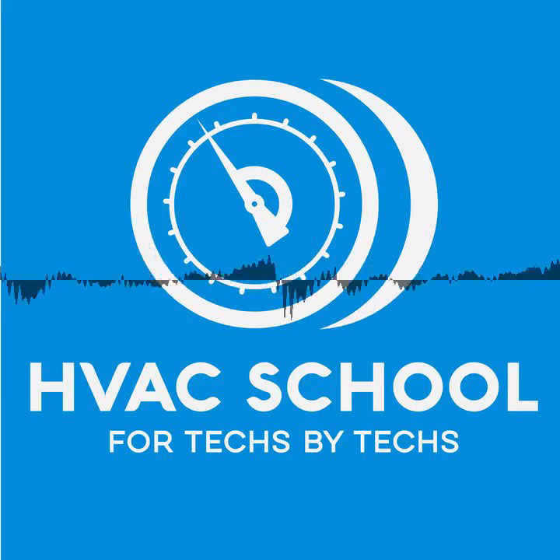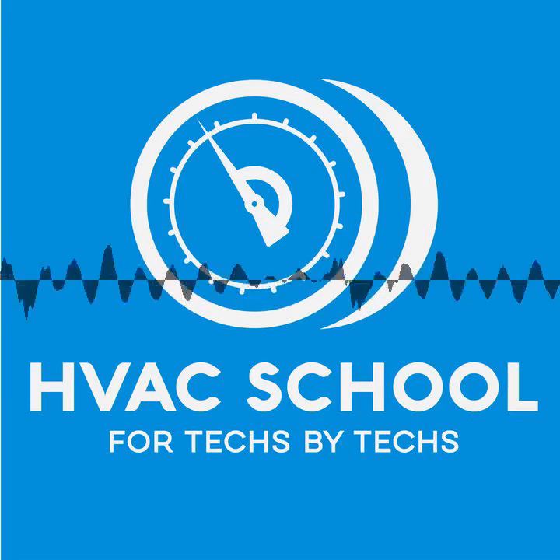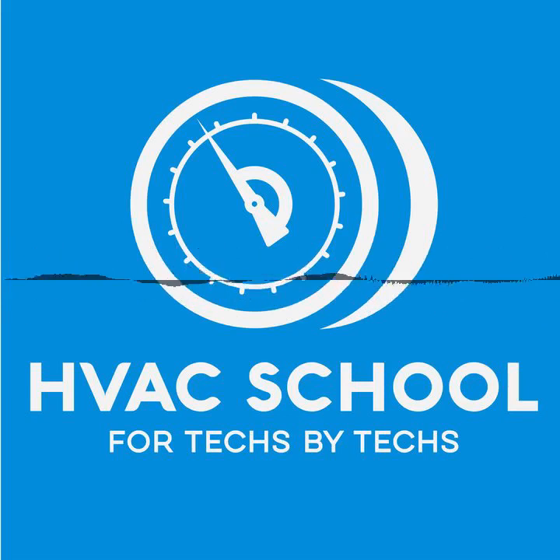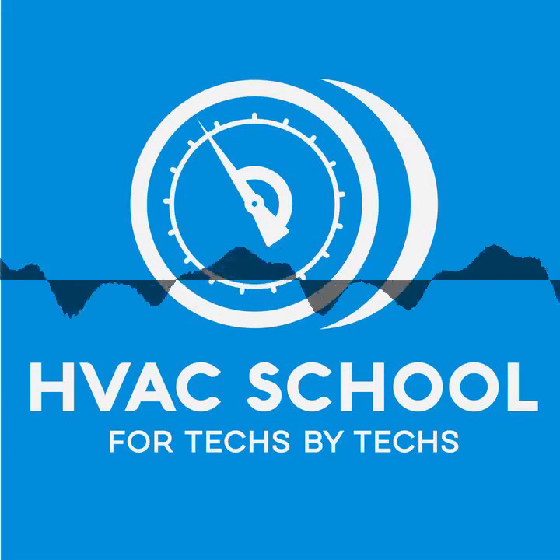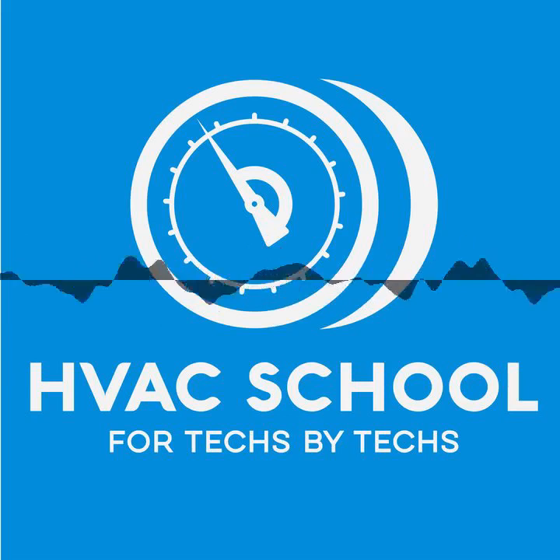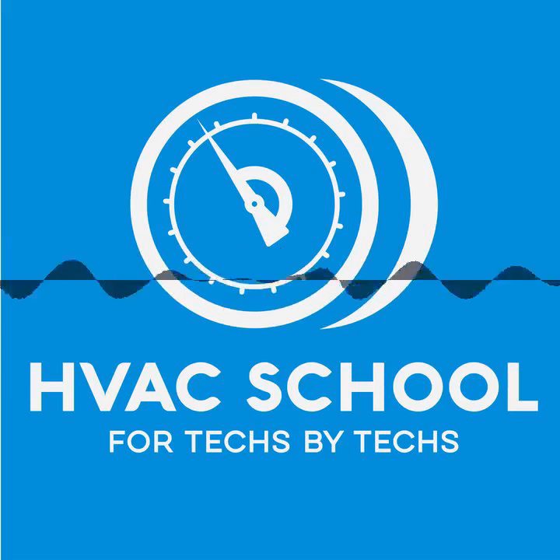And this side is your air side, outside, inside, and the before and after, or the return and supply conditions. So having something that actually gives you a wet bulb reading or some indication of humidity in the air is huge because let's face it, we're in a dry bulb driven world, right? That's what your thermostat on the wall reads. It's dry bulb. And if you have high humidity in the air, you better hope you have a dry bulb load as well, like a warm ambient that's going to drive that system to dehumidify. Otherwise, you're not going to get anything unless you overcool your space. So right then and there, having that ability to measure wet bulb is huge. That's a big step up.